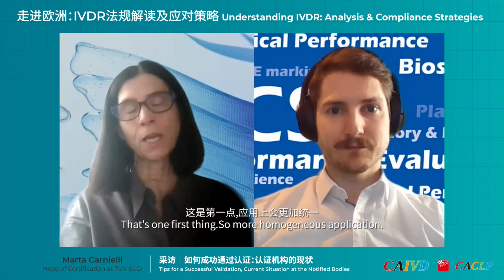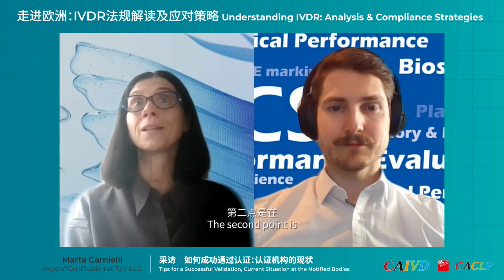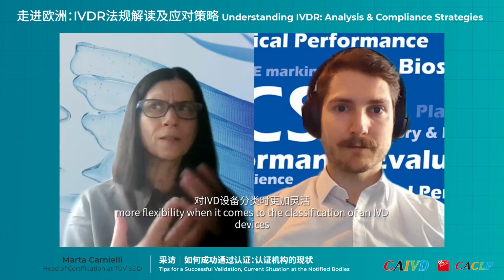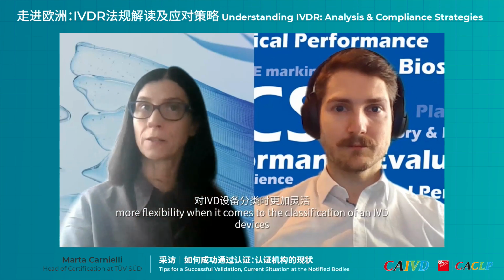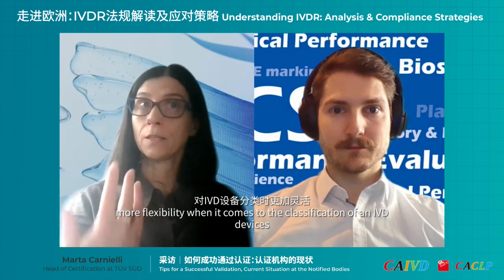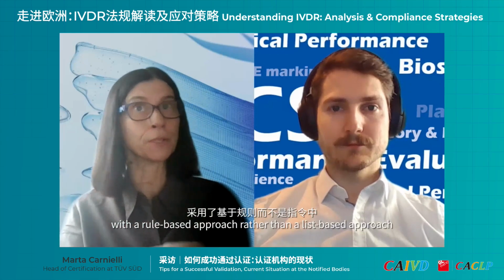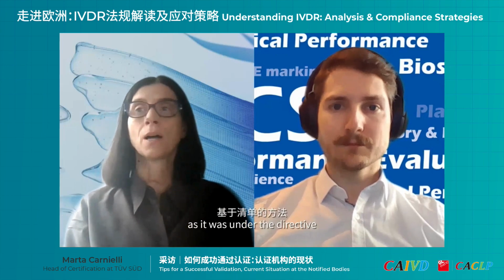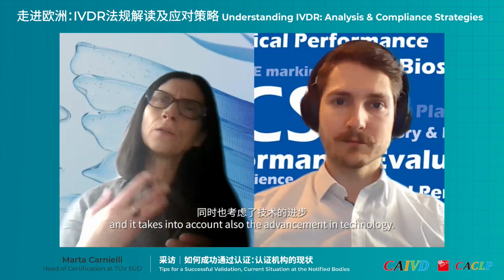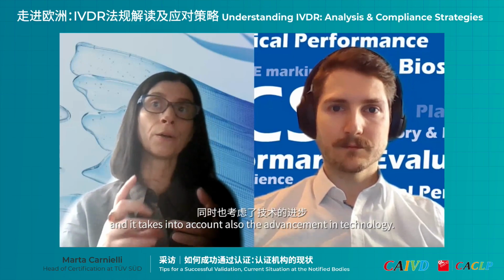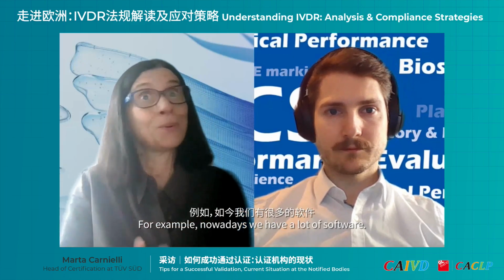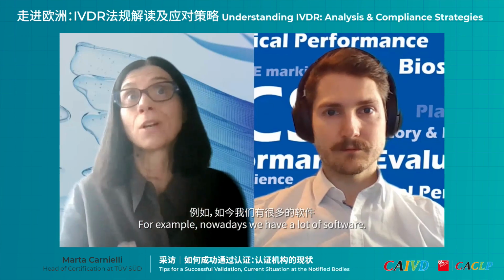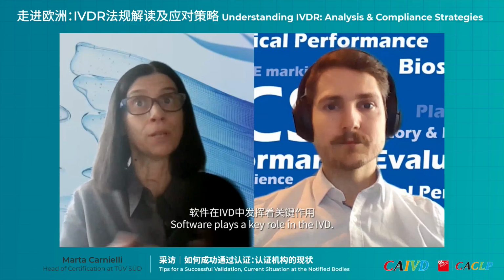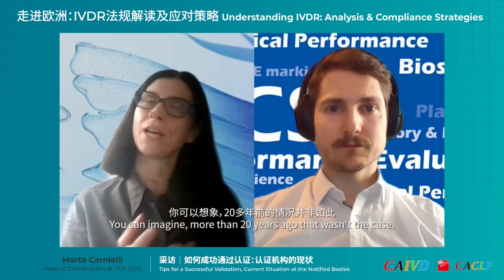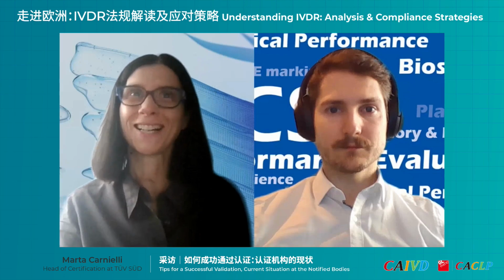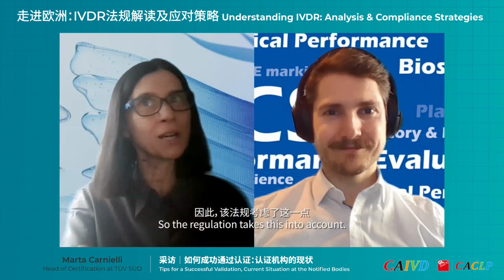So more homogeneous application. The second point is it's more flexible when it comes to the classification of IVD devices, with a rule-based approach rather than a list-based approach as it was under the directive. And it takes into account the advancement in technology. For example, nowadays we have a lot of software, and software plays a key role in the IVD. You can imagine more than 20 years ago, that wasn't the case. So the regulation takes this into account.